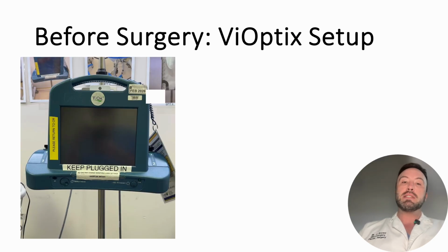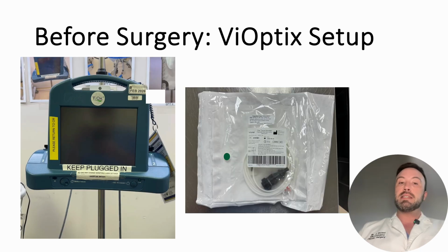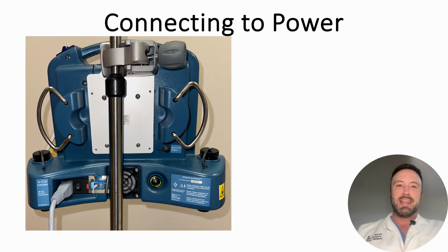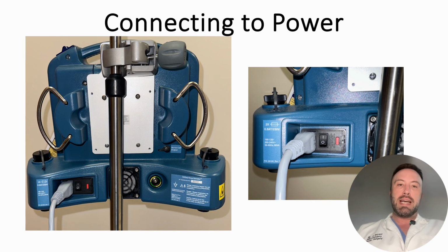Now, let's talk about setting up the ViOptix system in the OR. Before surgery starts, you'll want to be sure the ViOptix monitor and a sterile ViOptix probe sensor are in the OR. The AC power cord connects firmly to the rear of the console. Be sure to keep the ViOptix monitor plugged into an outlet as it has very limited battery life and cannot rely on batteries alone. The power switch should always be in the up position toward the 1.